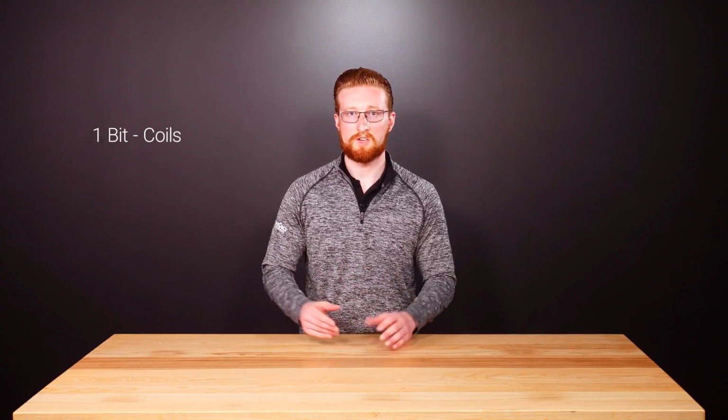Modbus ASCII and Modbus RTU use EIA 232 or EIA 485, which are twisted serial data cables that are low cost to transmit data. Modbus defines function codes and encoding schemes for transferring data as either binary points, 1 bit known as coils, or 16-bit data known as registers. This basic data packet is then encapsulated according to the protocol specifications for Modbus ASCII, RTU, or TCP.